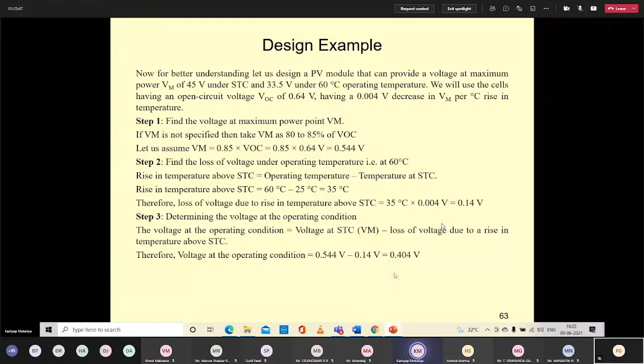Determining the voltage at the operating condition: voltage at operating condition equals voltage at STC minus loss of voltage due to rise in temperature above STC. So 0.544 volt, achieved in step 1, minus 0.14 volt from step 2, gives the voltage at operating condition for the panel working at this different temperature condition as somewhere near 0.404 volt.